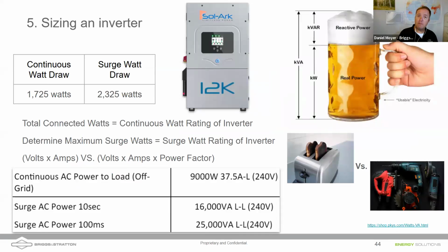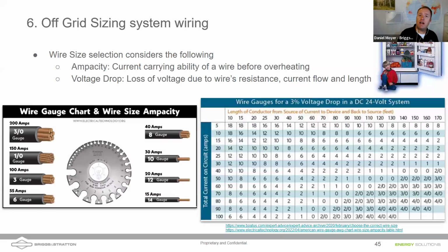We've got to make sure our inverter is powerful enough to handle the loads. Earlier we talked about our continuous watt draw and the surge because of the power factor. One thing that really contributes to the power factor is well pumps, booster pumps for your water system, and refrigerators. If we account for that VA, we know we only need 2,300 for this small system for the cabin. We know that the Sol-Ark unit can handle up to 9,000 watts continuous and up to 25,000 watts for 100 milliseconds, enough to start air conditioners and a lot of our big loads. So we're good on sizing there.